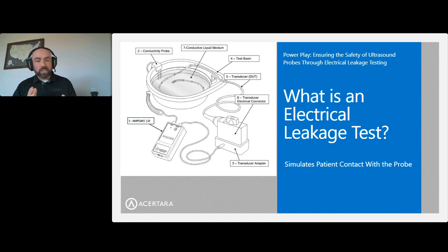What is an electrical leakage test? So you can see in this picture, you have a connector for the ultrasound probe that connects into the electrical leakage connector. That gets connected to your electric leakage tester. And then from the electric leakage tester, you have a conductivity probe that gets submerged in a conductive fluid, either water with a salt bath or disinfecting fluid. You can make a measurement. Most of these devices will put a reference voltage into the fluid to ensure that you can actually conduct a test accurately, and then it will run through a test and produce a value that will indicate that the probe passes or fails.